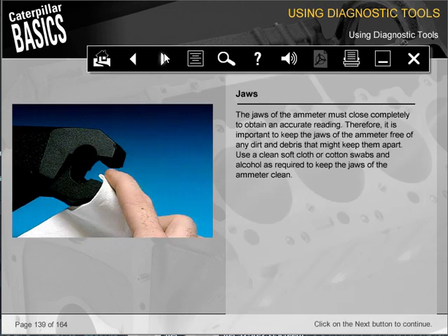The jaws of the ammeter must close completely to obtain an accurate reading. Therefore, it is important to keep the jaws of the ammeter free of any dirt and debris that might keep them apart. Use a clean, soft cloth or cotton swabs and alcohol as required to keep the jaws of the ammeter clean.